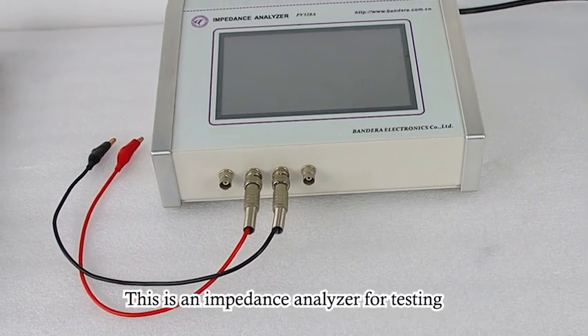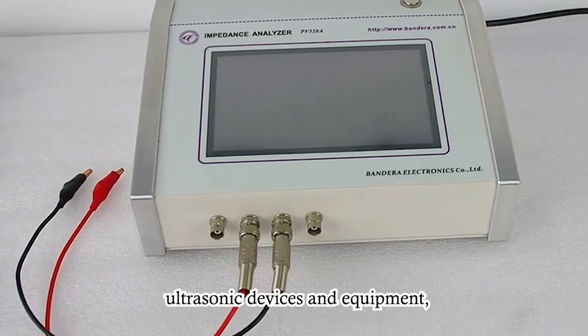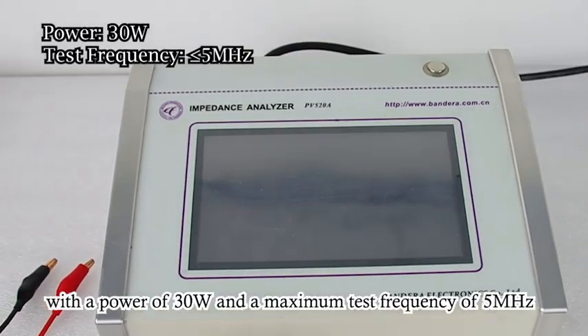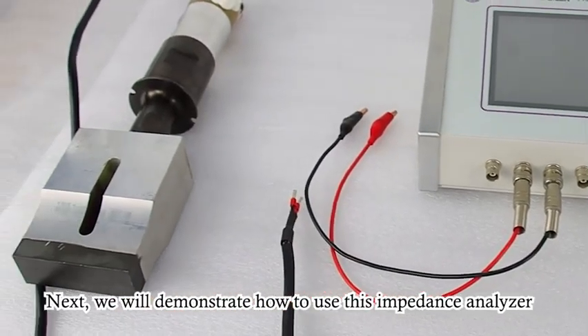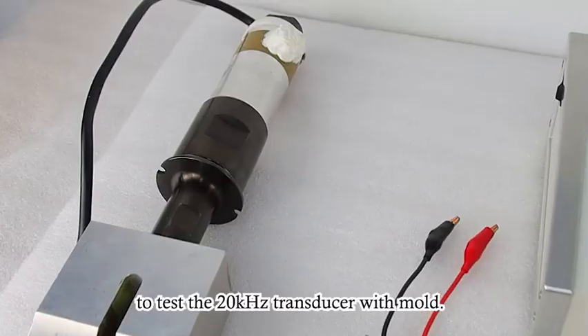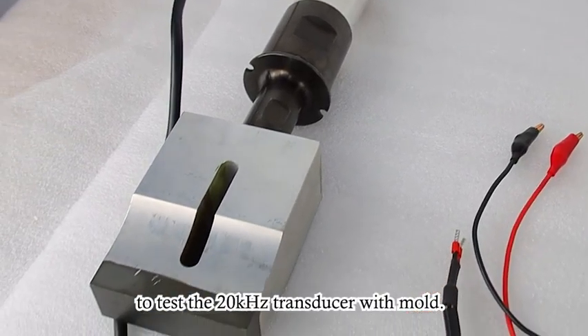This is an impedance analyzer for testing ultrasonic devices and equipment, with a power of 30 watts and a maximum test frequency of 5 MHz. Next, we will demonstrate how to use this impedance analyzer to test the 20 kHz transducer with mold.